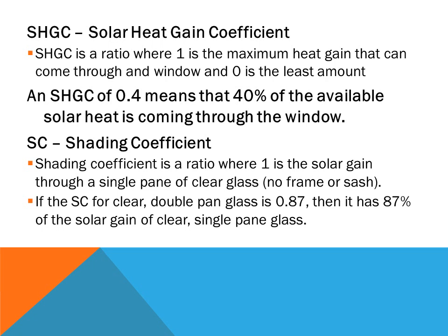The Shading Coefficient, abbreviated SC, is a ratio where one is the solar gain through a single pane of glass, not including the frames or sashes. For example, if the shading coefficient for a clear double pane glass is 0.87, then it has 87% of solar gain through that type of glass.